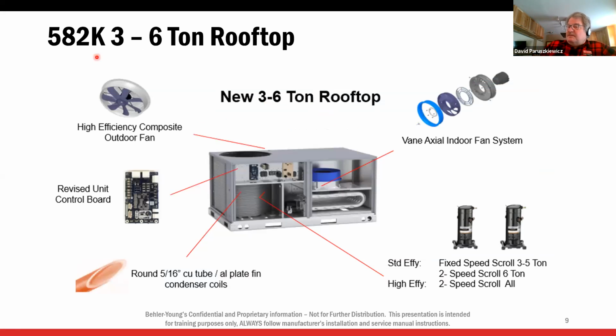So we're going to jump into the blower first on a 582K. These are the small package rooftop units, 3 to 6 ton. They've been out now for a couple of years. Scroll compressor, but the big difference here is this new vane axial indoor fan blower motor. This is a vane axial blower motor. You may have seen it. It's a big blue ring. Let's take a look at it in a minute.